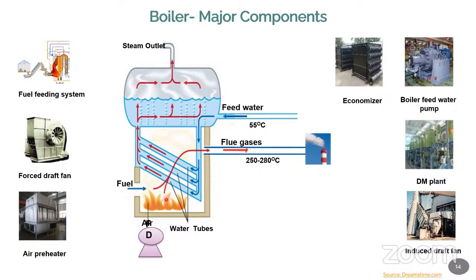Now, the second important point: we need 100% combustion. If you want proper combustion, then we have many advantages. If 100% combustion takes place, the main advantage is that 100% of the heat is transferred to your water. Number two, the amount of ashes produced will be much lesser. Number three, your water will very quickly convert into steam. So these are all the direct advantages.